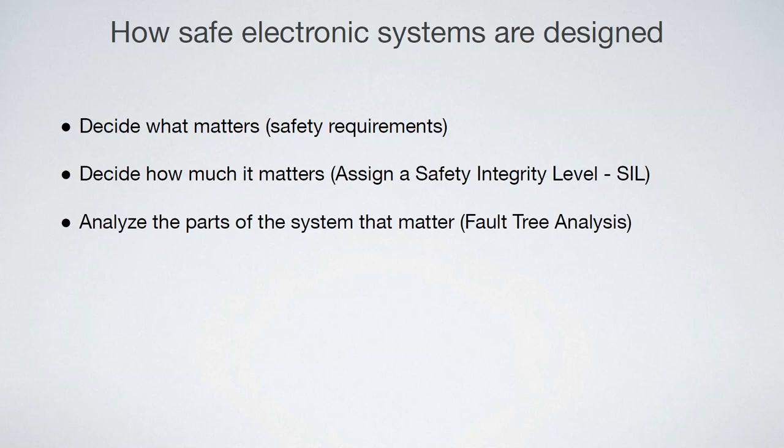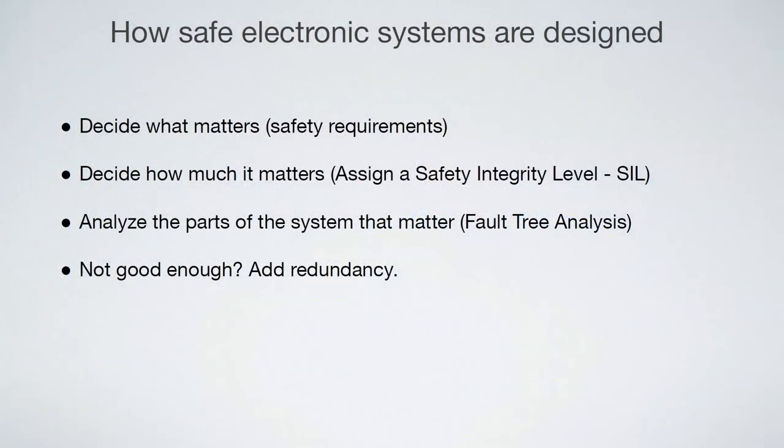With that in hand, they'll pick apart their system design and figure out which parts could contribute to violating the safety requirement in question. You do this by forming a tree and saying: if this faults, then I will cause a fault up here, and so on. That's called a fault tree. Then they ask: based on this analysis, have I met the requirements laid out in whatever standards they're looking at for the safety integrity level they decided upon? If it's not good enough, maybe they'll buy a more expensive part or add some kind of redundant system.